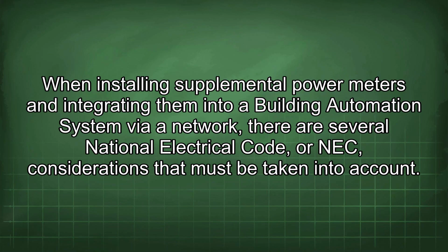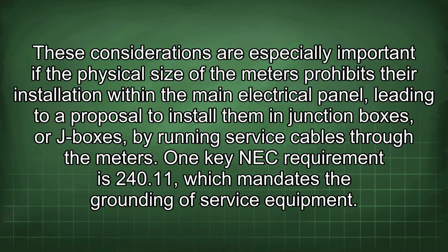When installing supplemental power meters and integrating them into a building automation system via a network, there are several National Electrical Code, or NEC, considerations that must be taken into account. These considerations are especially important if the physical size of the meters prohibits their installation within the main electrical panel, leading to a proposal to install them in junction boxes, or J-boxes, by running service cables through the meters.